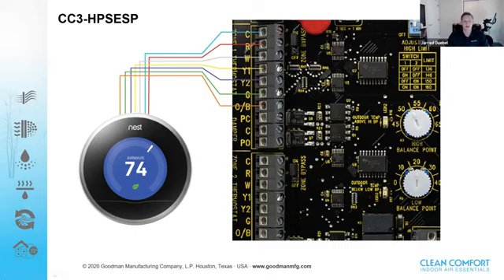So on the zone bypass, I mentioned earlier that we give you the option to shut off specific zones. Sometimes people ask the question, well, if you're bleeding air into zones, are you going to over-condition specific spaces? The response is, on 99% of systems, no. The reason being is that at 0.35 inches of water column, and we're cracking those dampers typically about 6 to 8%, the amount of air or pressure we're leaving is minimal. It's not like a zone that's calling, where we're pushing a good amount of airflow into that space.